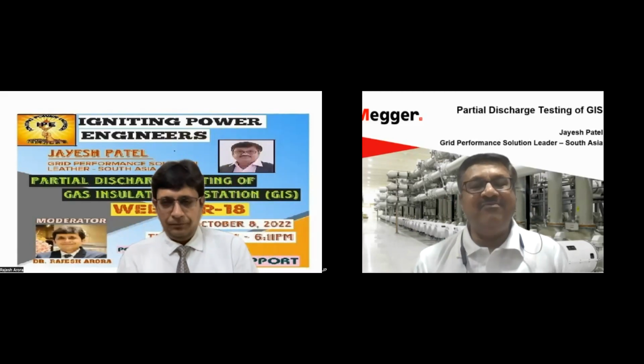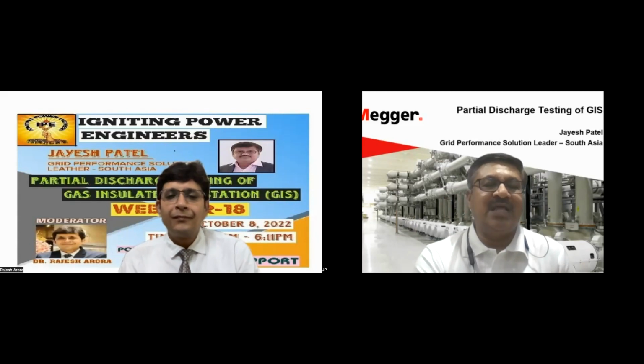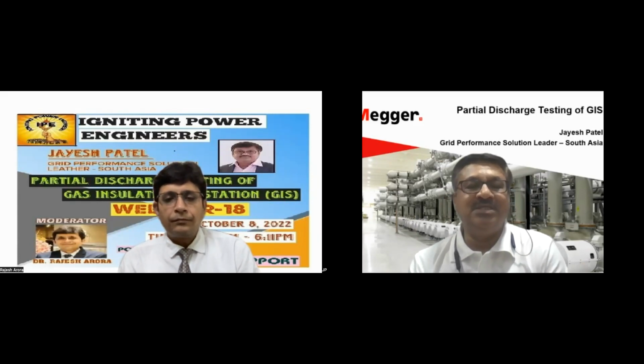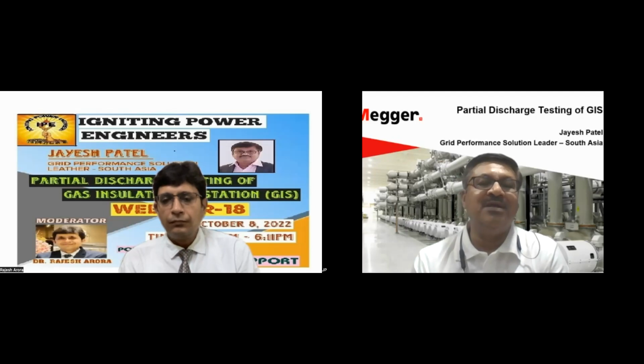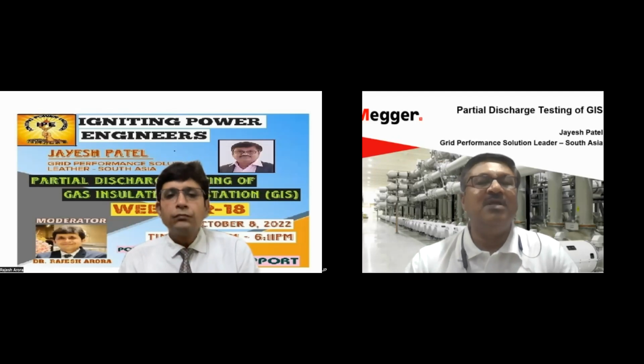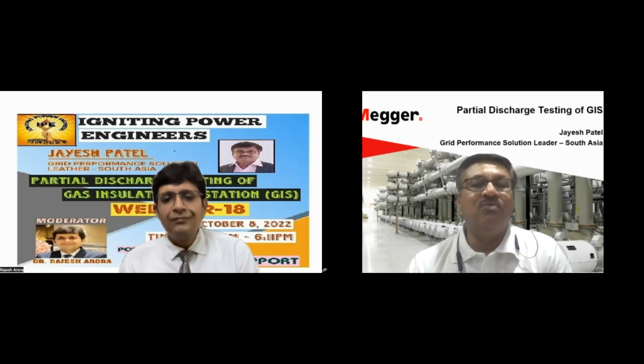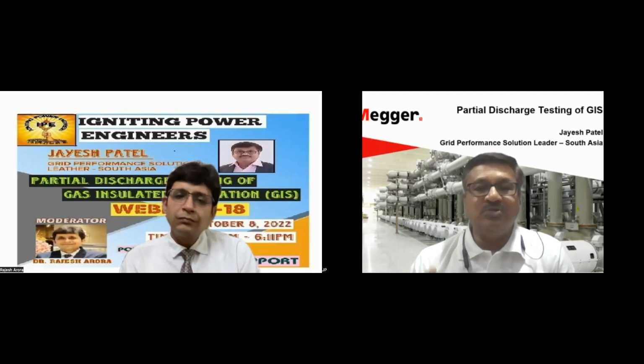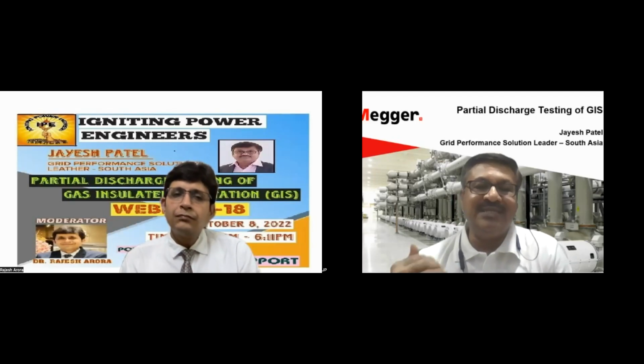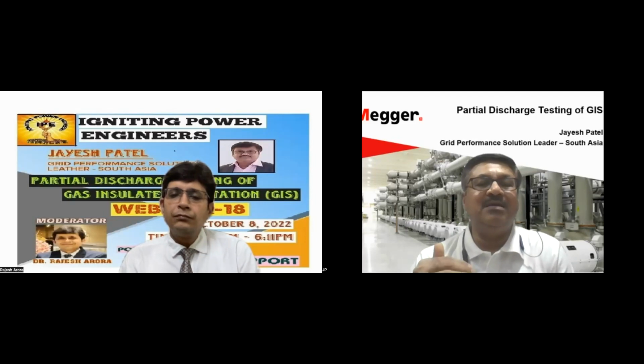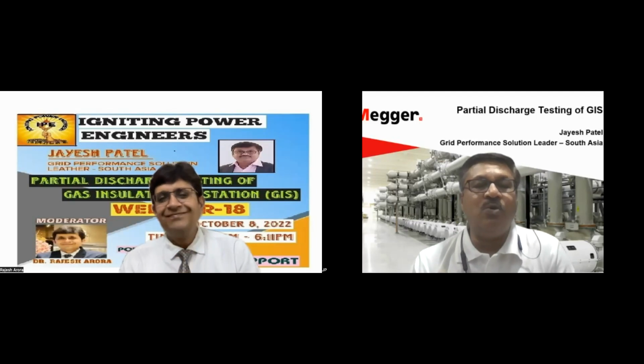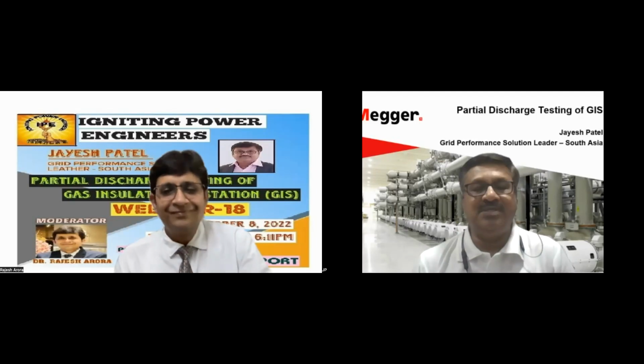Yeah. See, for every asset, sometimes transformer, sometimes cable, sometimes GIS, or maybe a rotating machine, some standards have been set on what is the acceptable level of partial discharge, because we cannot say that on the first day it would be zero. There would be some level of partial discharge. So what should be the acceptance criteria on day one? What is the bare minimum acceptable? CIGRE 654 is the standard which has laid down those guidelines, and it says that in GIS 5 pC and below is acceptable. So you should worry only when the PD is more than 5 pC.